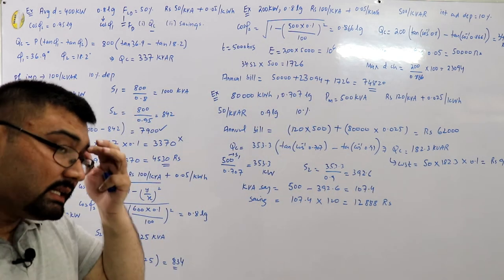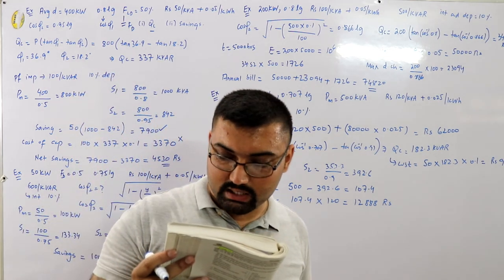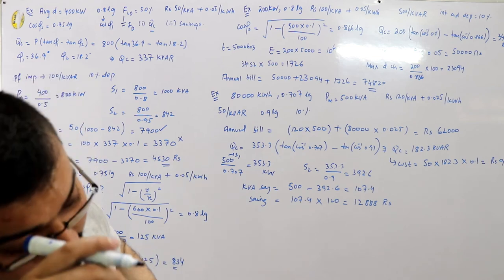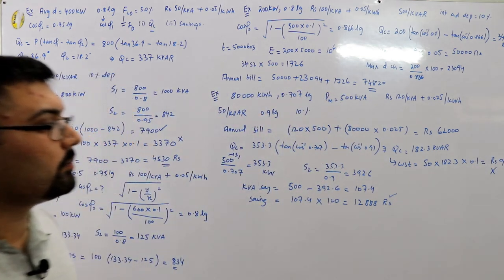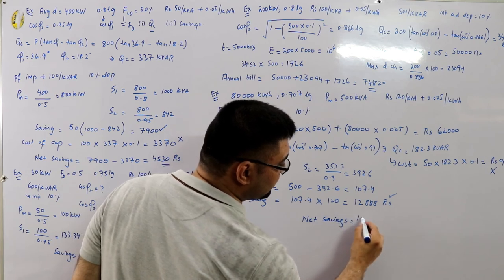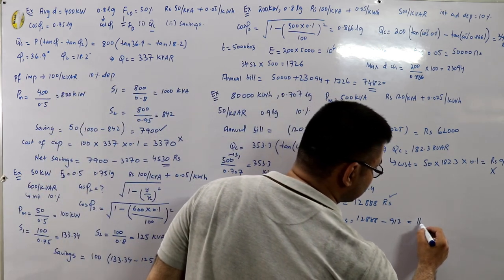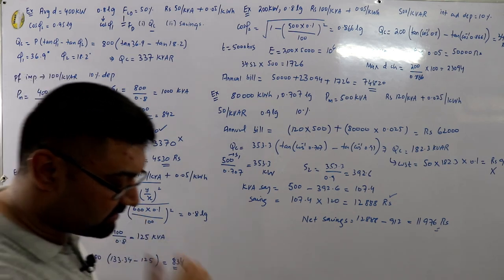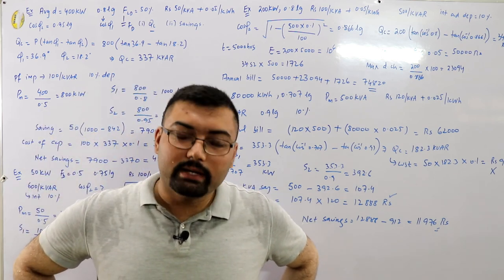The units consumed are the same before and after power factor correction, so the energy cost remains unchanged. Net saving = savings from kVA reduction − cost of phase advancing equipment = 12,888 − 912 = 11,976 rupees annually. That is the amount of money saved per year.